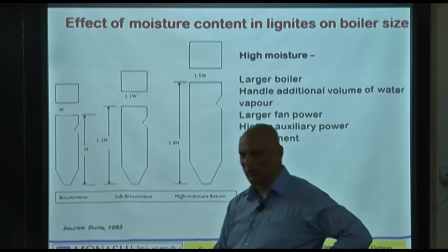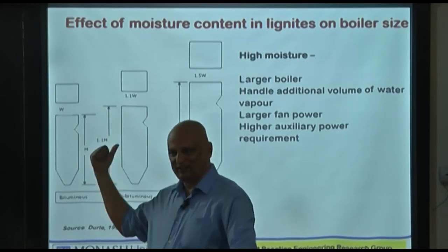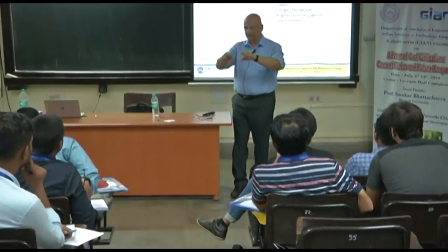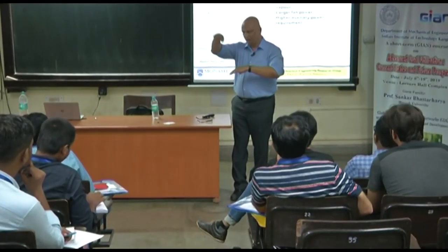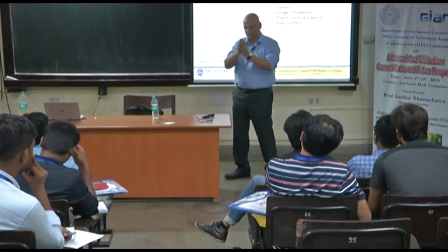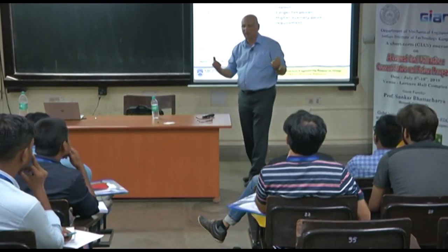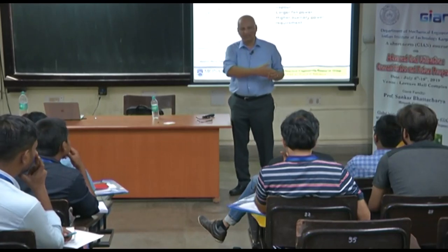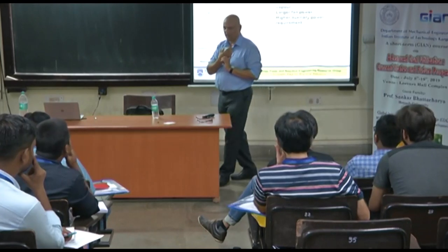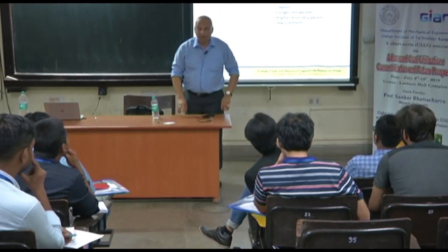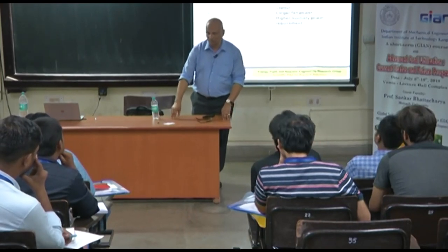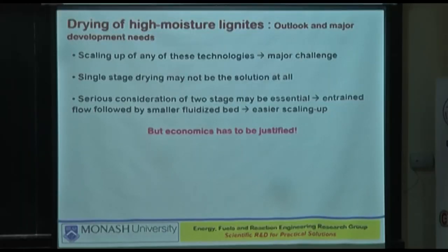So it's the specific volume of water vapor that is the key. The pulverized coal-fired boilers all operate, except where you have the fireball in the slagging zone, at slight vacuum, where everywhere else is more or less atmospheric pressure. So there is no pressure to compress the volume. If you have more water vapor, it will be higher specific volume compared to the other gases, which is predominantly carbon dioxide. Because the product of combustion is predominantly carbon dioxide and water vapor, plus ash and unconverted gases and some gaseous pollutants such as carbon monoxide and nitrogen oxide, which we cannot talk about.